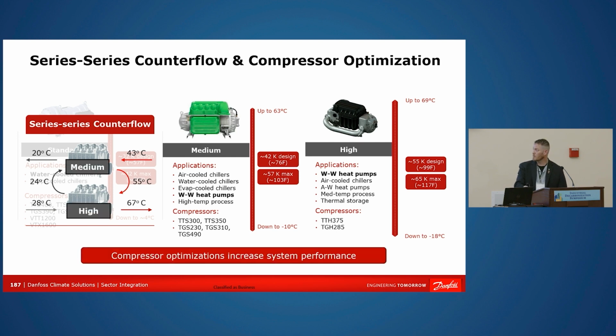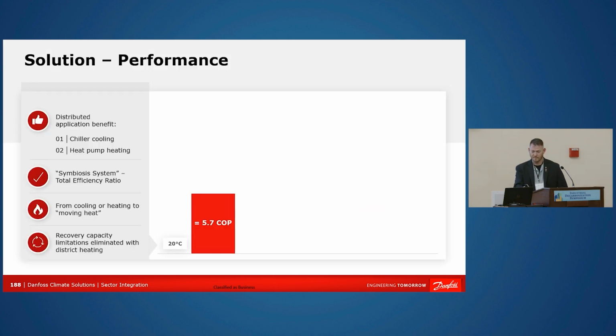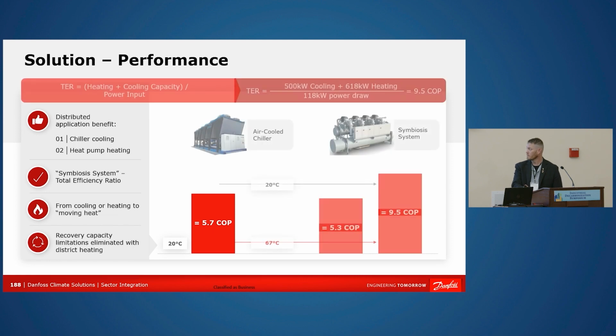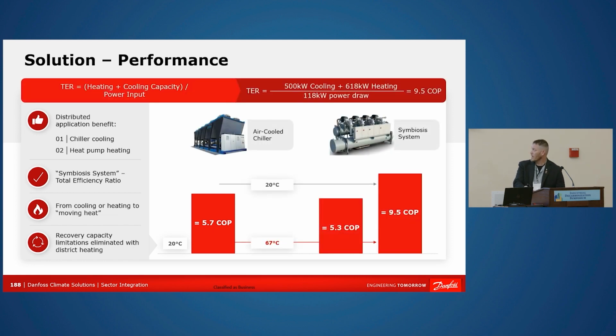So we have the medium and the high. These are the compressors that you can see that we utilize for the system. Also with this performance, at 20C, we're at 5.7 COP. And with that 20C in and 67C, which is a higher temperature going into it, with the 5.3 COP, we'll get a 9.5 COP at the end of that.